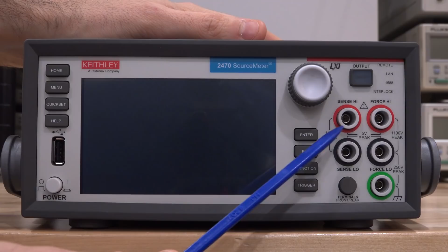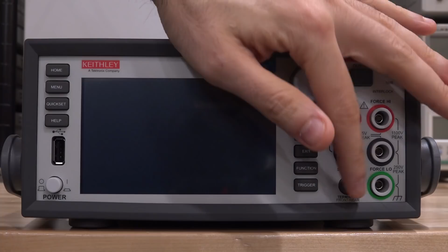There are a few lights in the back here, particularly the interlock I find to be very useful, because for an instrument like this that goes up to 1000 volts, you want the interlock to be something that's visibly available to you to make sure that your setup is actually correct. We also have force in and sense as well for a 4-wire measurement, and the chassis ground. There's also a button here in order to do front and back. This is actually a soft button, so there's some mechanical switching inside that enables for you to go from the front panel to the rear panel, and they probably have done this in order to not have to have the 1000 volt directly on a switch over here, which kind of makes sense.